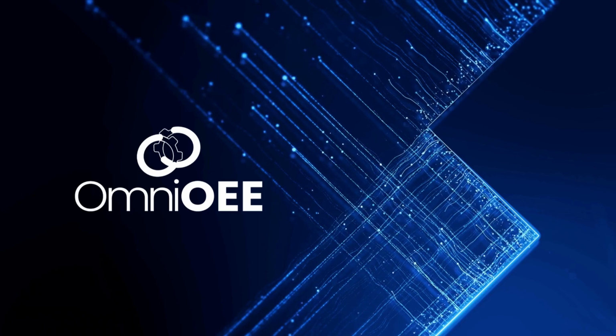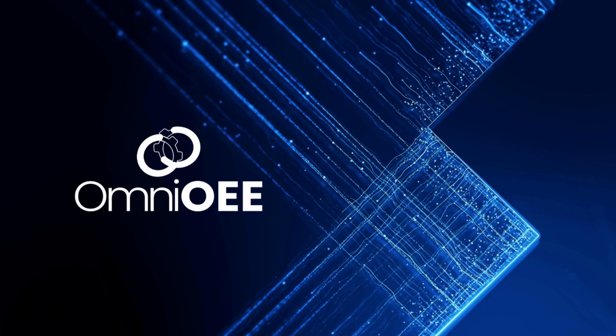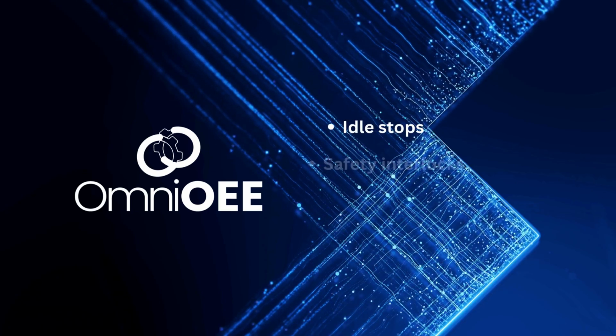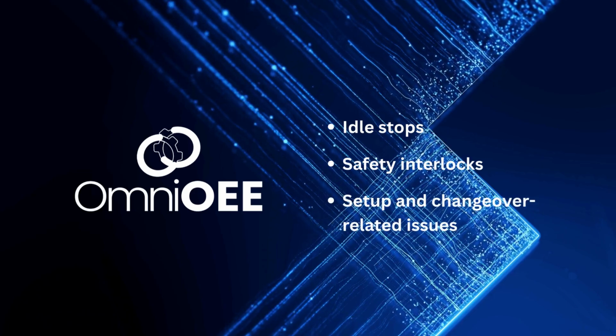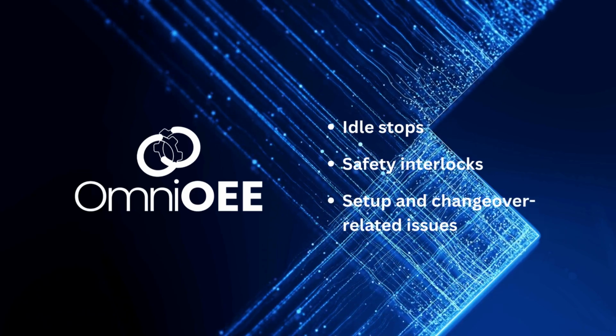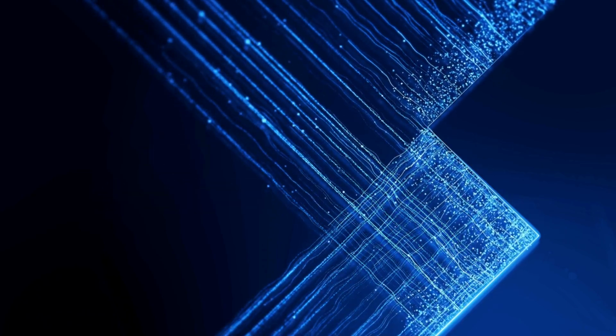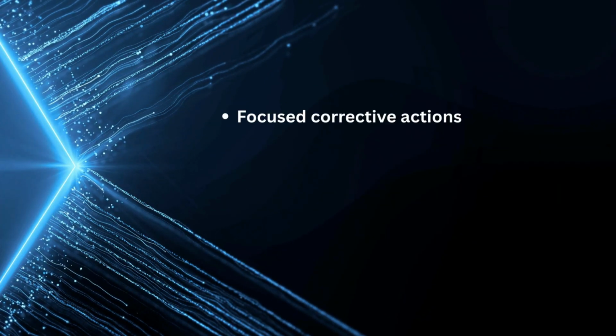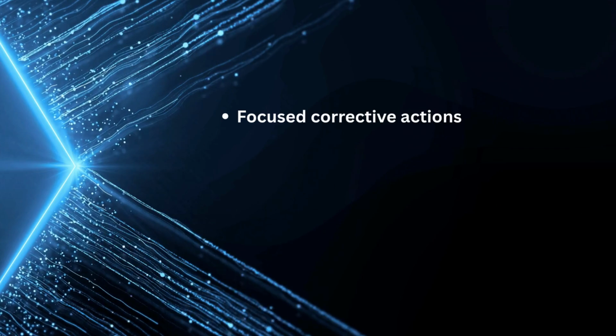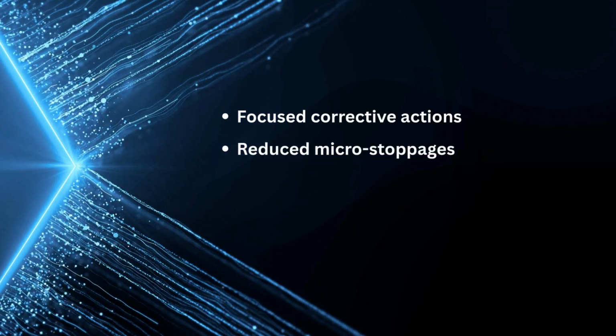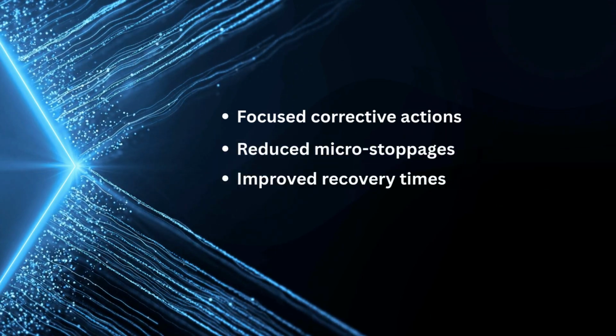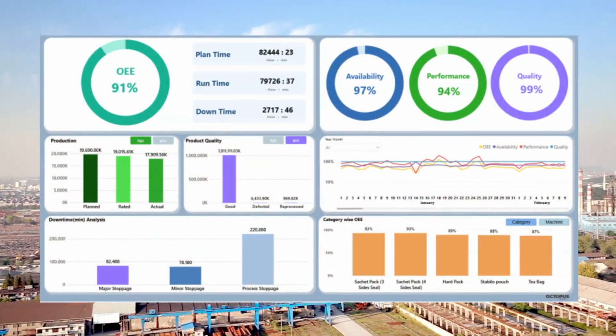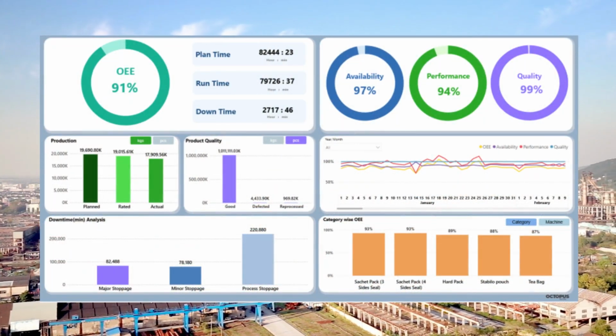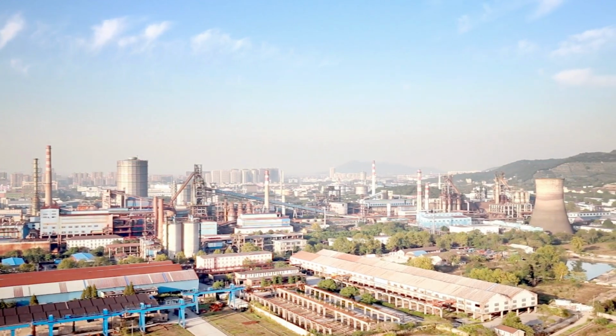Let's go even deeper into availability. Using the root cause analytics dashboard, OmniOEE pinpointed idle stops, safety interlocks, setup and changeover related issues. These issues were previously seen as routine operational noise. With clear visibility into frequency and duration, teams were able to take focused corrective actions. By addressing high-frequency issues, micro-stoppages were reduced, recovery times improved, and overall runtime stabilized. In fact, one of our customers scaled up production with additional machinery because their OEE was now world-class.